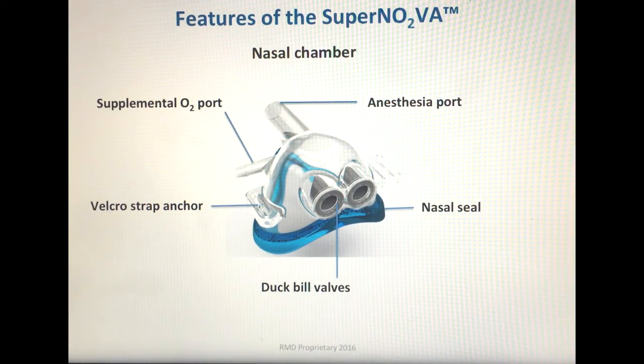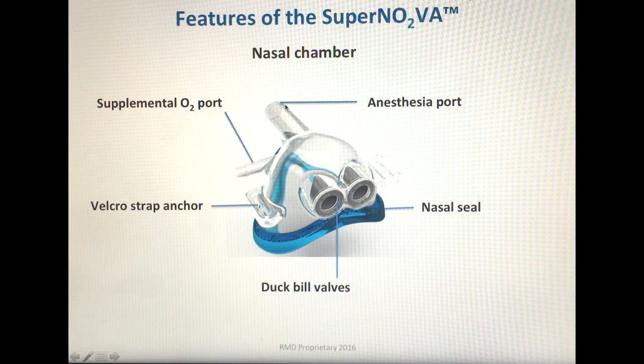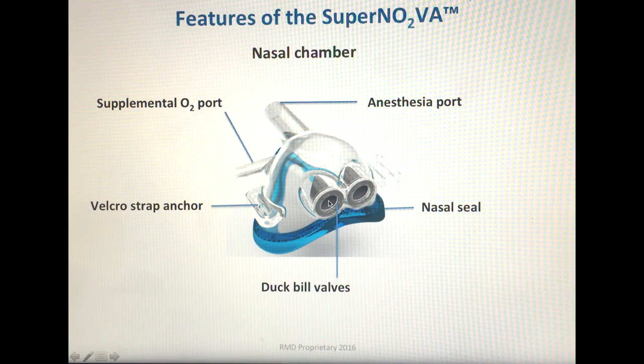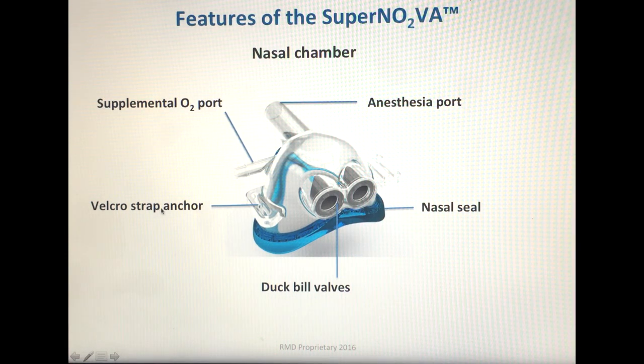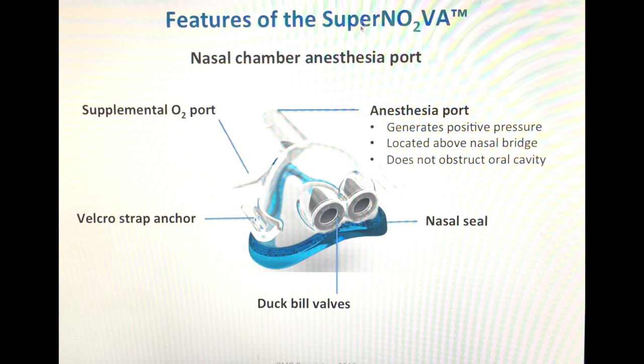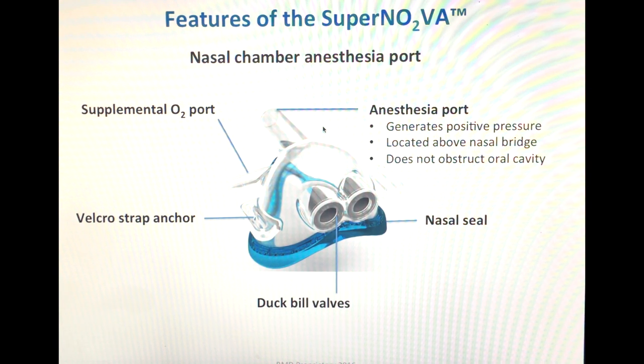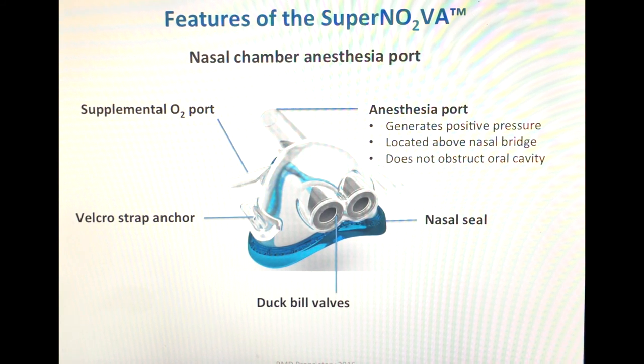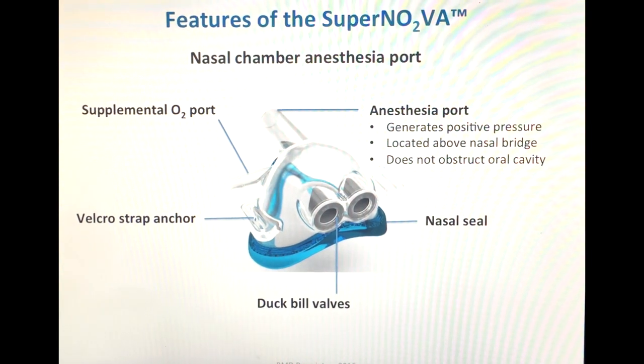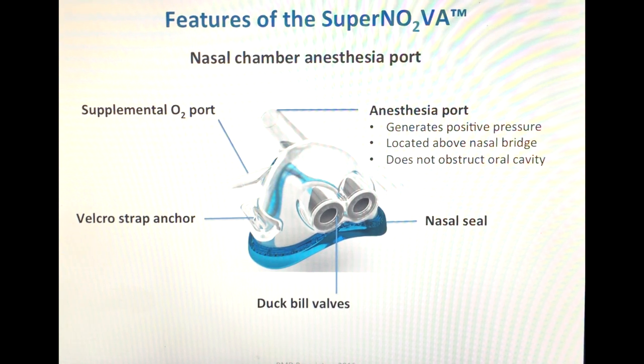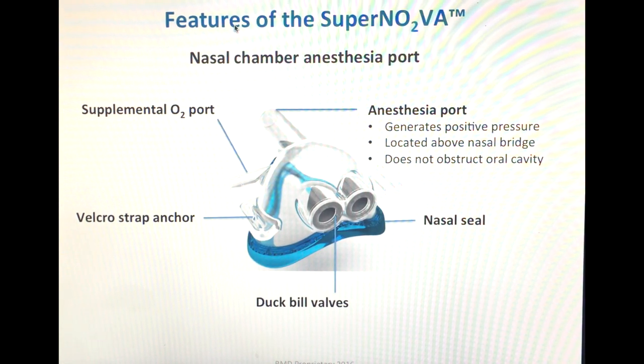Let's discuss the features of the SuperNO2VA, starting with the nasal chamber. Key features include the anesthesia port, the nasal seal, the duck bill valves, the Velcro strap, and the supplemental oxygen port. The first unique feature is the location of the SuperNO2VA's anesthesia port. On typical masks, the anesthesia port is located in the middle and extends vertically, which would obstruct the clinician's view during intubation. The SuperNO2VA's anesthesia port was specifically designed to be located above the nasal bridge, parallel with the face, allowing for continuous ventilation during laryngoscopy.